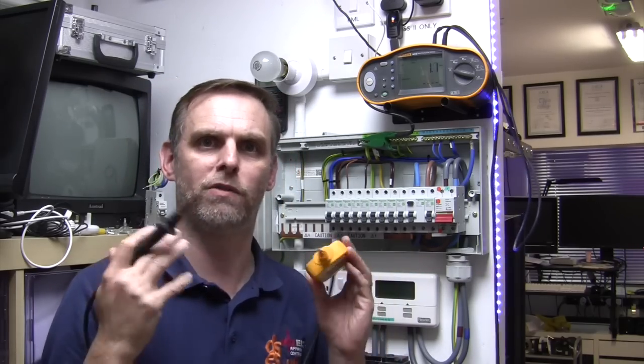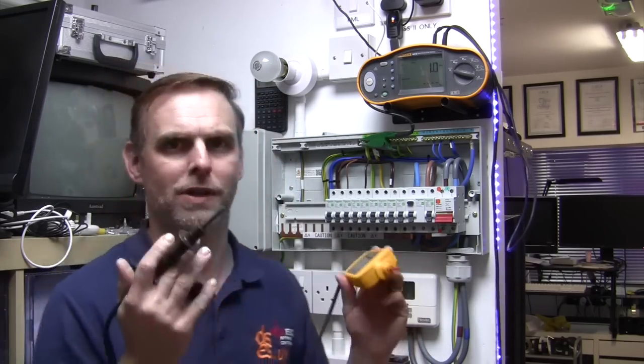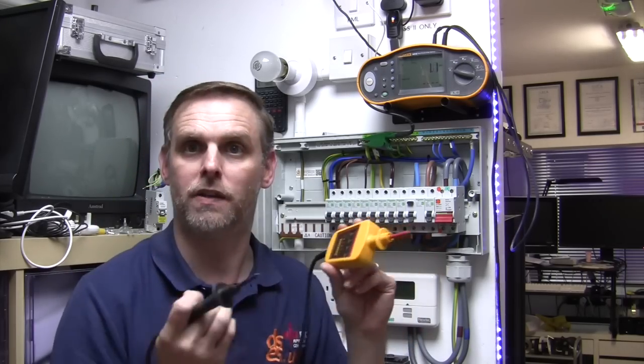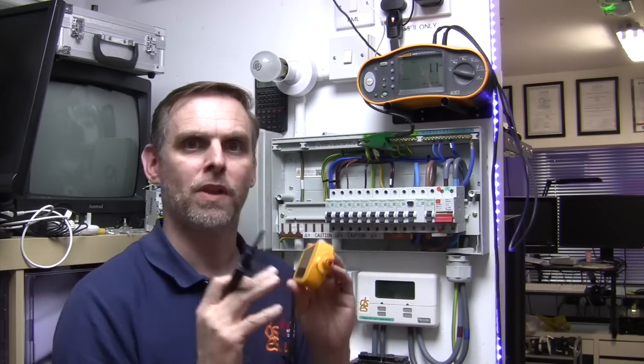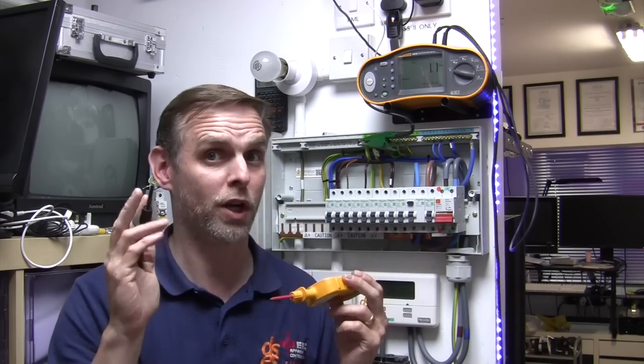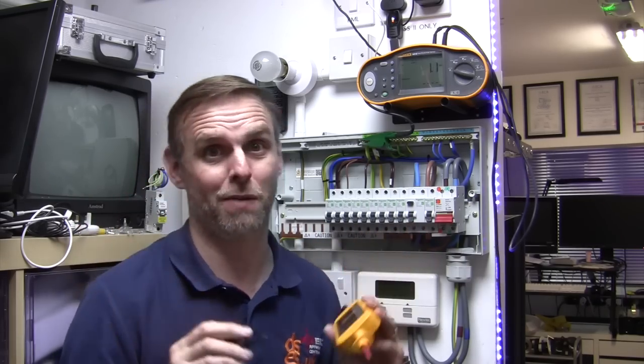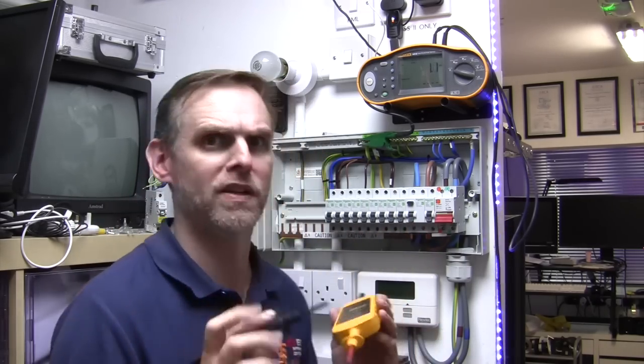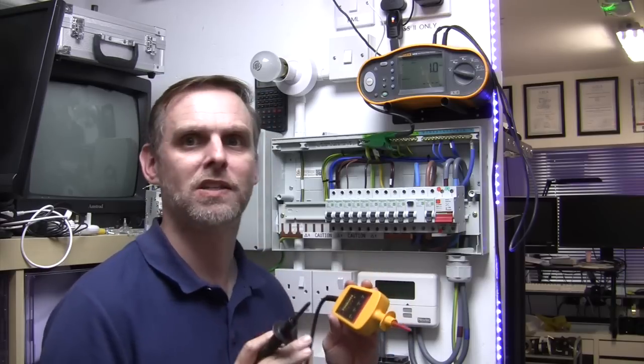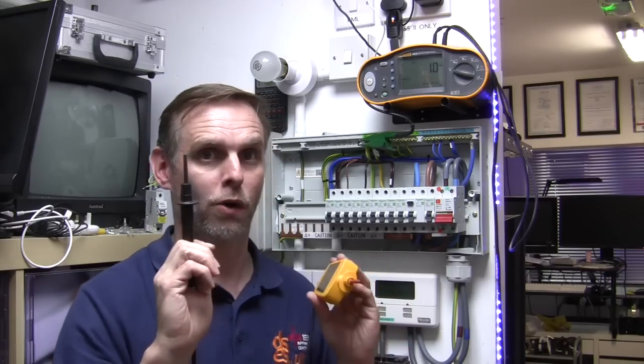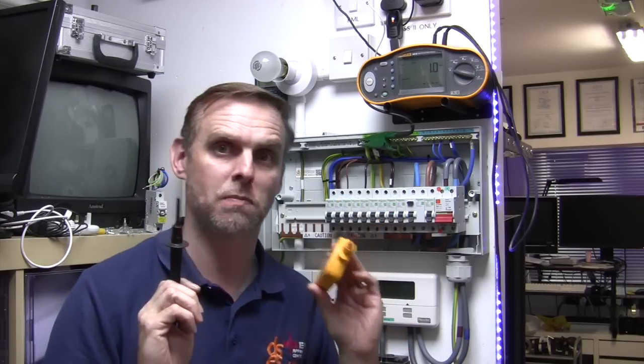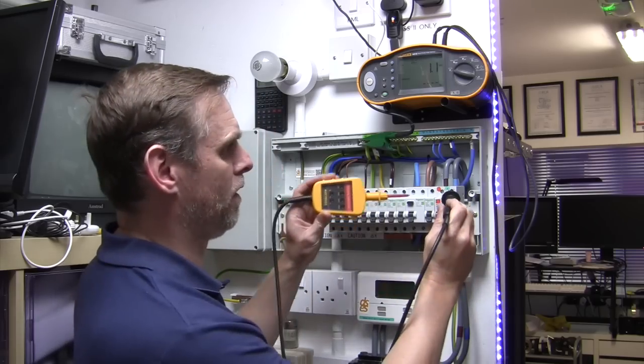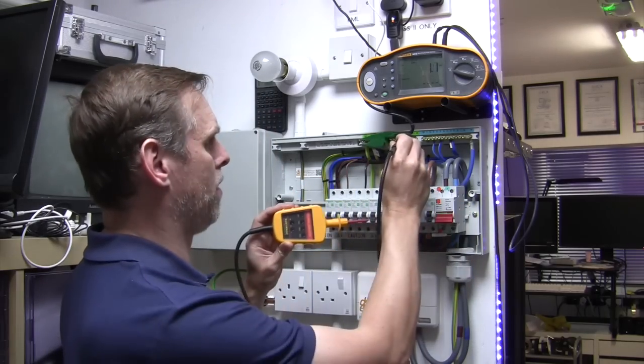The actual voltage that you find on the end of the probe will depend on the resistance of the load, the load in this case being the electronics inside the indicator instrument itself. And the instrument of course may be fused or contain protection to prevent a shock from occurring if you do touch that, but I'm not about to test that theory for the purposes of this video. Suffice to say that when single phase testing, connect the black probe to the neutral or earth first and the red probe to the suspected live part under test, and you should avoid any nasty surprises.